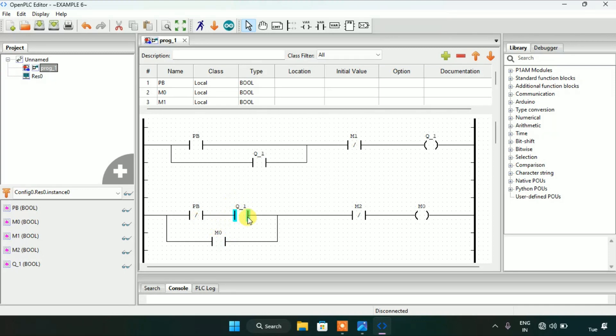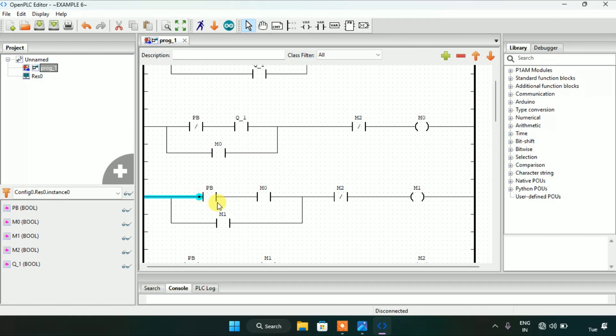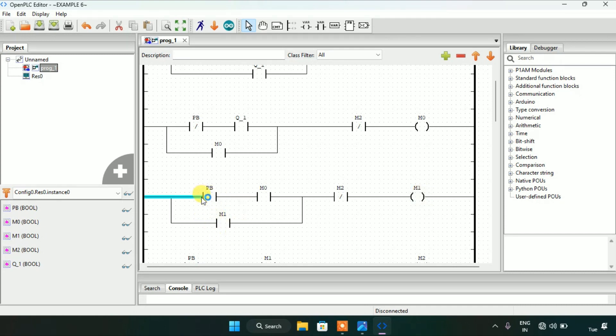In the third rung I created a normally open contact PB in series with M0 — which is a normally open memory bit contact — then M2 as a normally closed contact, and M1 as a coil. I latched M1 in parallel with the push button PB and memory bit M0.